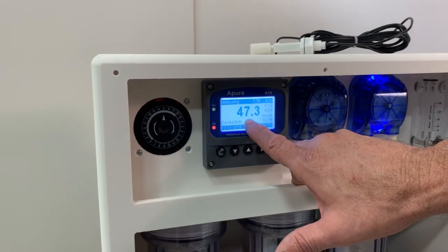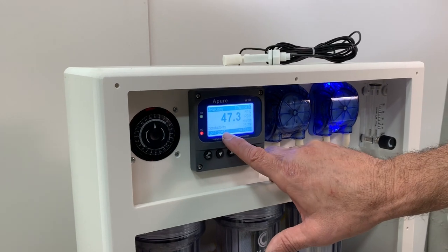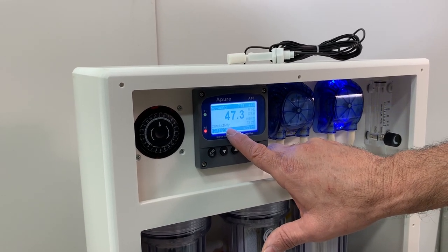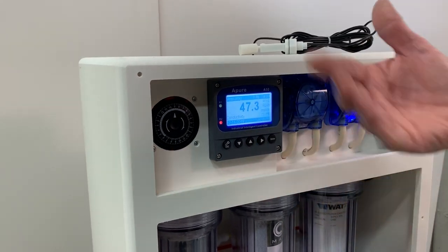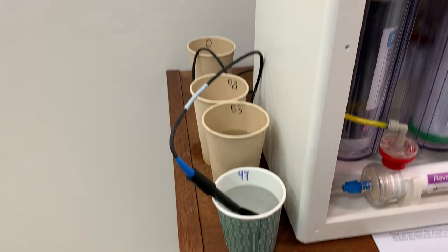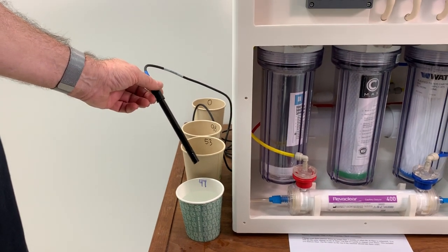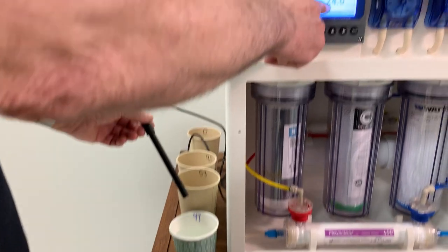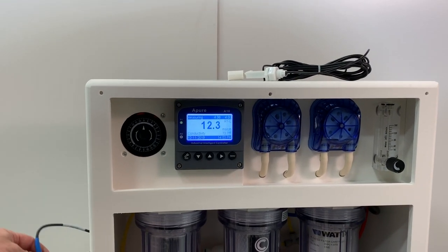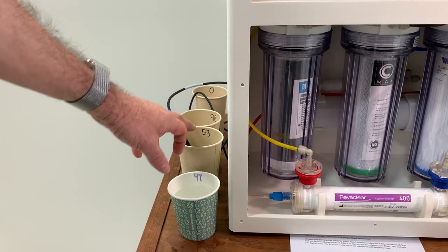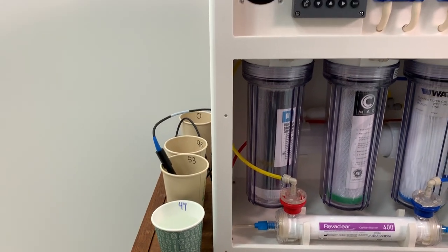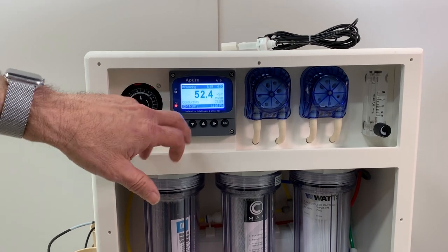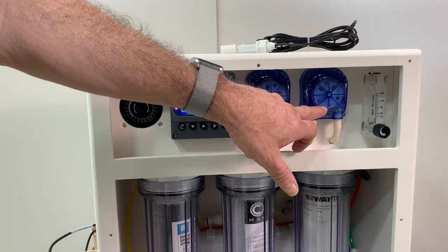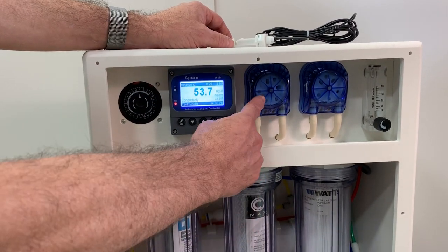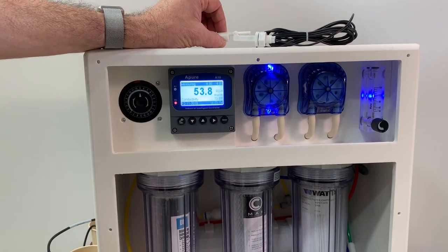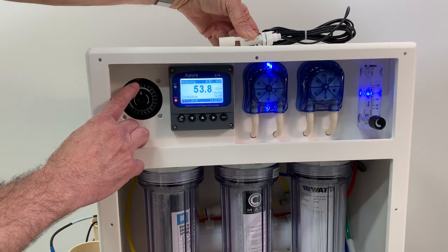And now you see it's 47.3. If you remember, we were at 44 to turn it off, and we were at, I believe, 51 as our set point. So because we're not below 44, the machine is still operating and the salt pump is working. If I were to take this probe out for a second, and it dropped below that 44, it shuts off the machine. If I were to put the probe back in the aquarium at 53, it takes a little time for the water to get all around the sensor and start registering. You notice now we're past that 51, so it doesn't need to turn on the salt pump. If we wanted to see this thing change water again, all we have to do is drop the float switch. Now, again, it's doing this because we're on a timer segment.